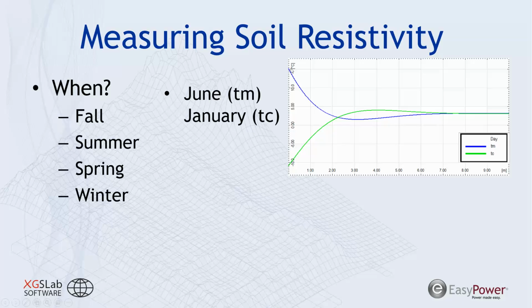We have relatively warm temperature that starts to creep down to the average soil temperature as we go maybe 6 meters deep. Now, in the winter in January, we have really cold soil conditions, and we see this start to creep up and level out at the same point where we begin to match our deeper soil temperatures, maybe 6 to 8 meters.